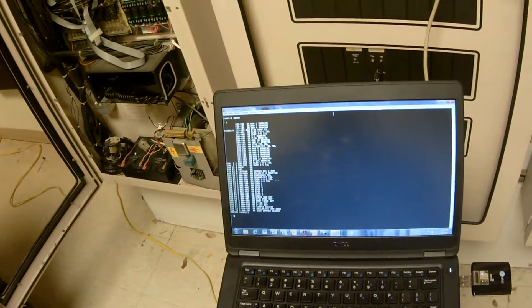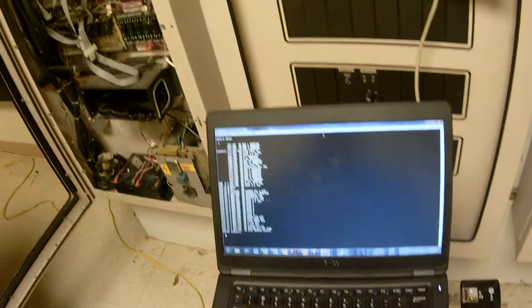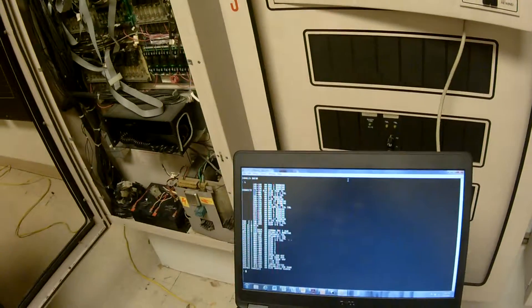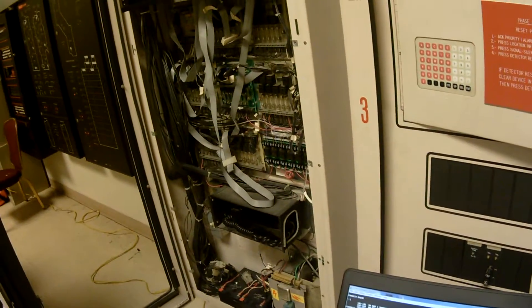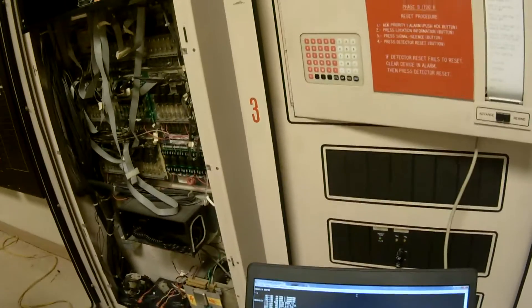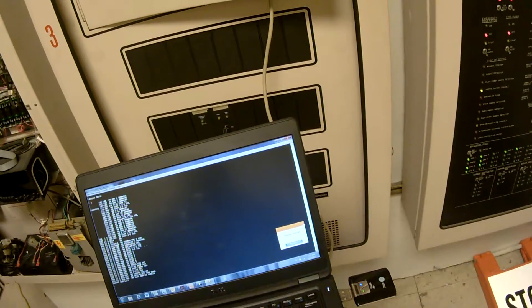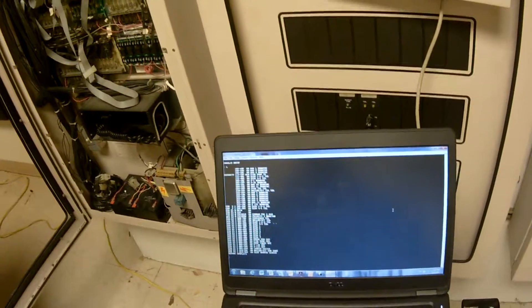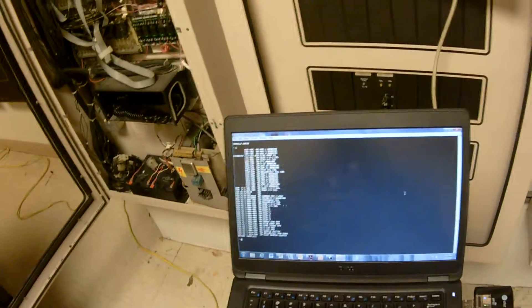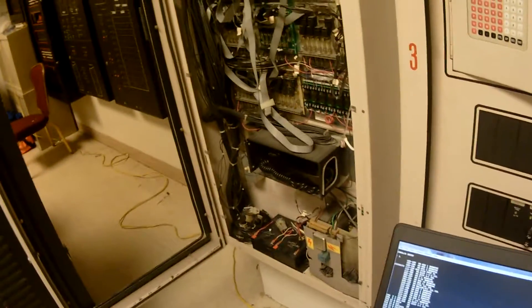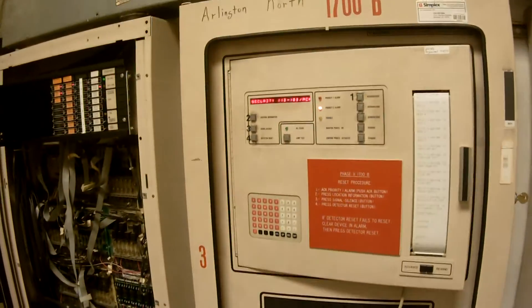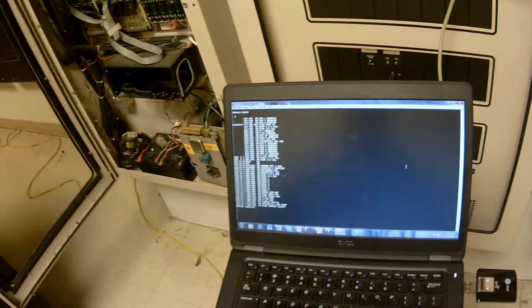Now, just to clear up some things, just for some basic functions of this panel. What's really cool about this panel is I get to interact with it. I get to ask questions and it talks back to me. We go back and forth, not like some of the newer panels where you have to put the program in it and go out there and test it and see if it works or not. This one here, we can disable everything and we can test it and we can watch everything that happens and verify that it is going to happen before we actually do our real test. And we'll be more confident when test day comes along that everything's going to work okay.